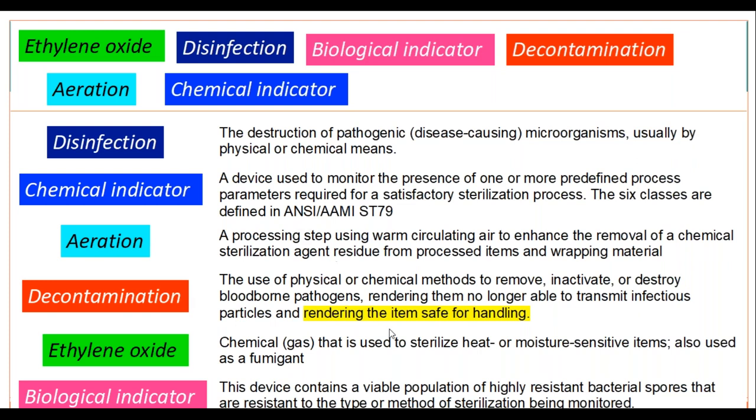Aeration: a process step using warm circulating air to enhance the removal of a chemical sterilization agent residue from processed items and wrapping material.